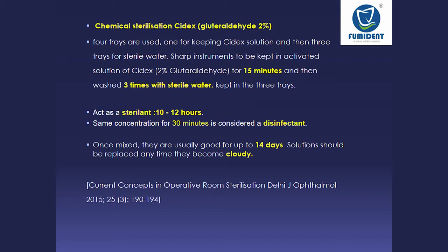You have to look at the manufacturer's instructions for how much time you have to immerse your instruments for sterilization. For example, if you are using Cidex solution, you need to keep them for 10 to 12 hours for sterilization and 30 minutes for disinfection.